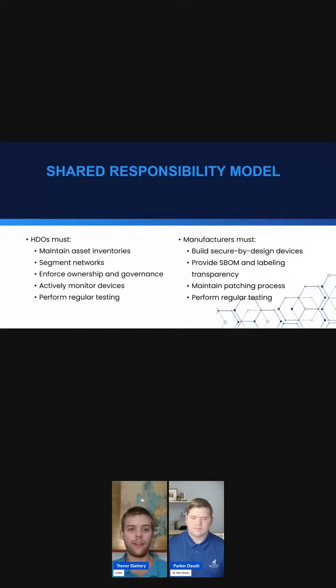Who is going to run these? We need to be sure that we are monitoring any devices for known vulnerabilities. This can be through trusted sources such as CISA or the FDA, or information sharing centers such as HISAC, which is a great option. And the hospital itself needs to perform regular testing. This is something that goes over to the medical device manufacturers as well, but it's especially vital that we have regular penetration testing, regular network testing, and we make sure that we have full coverage on both ends.